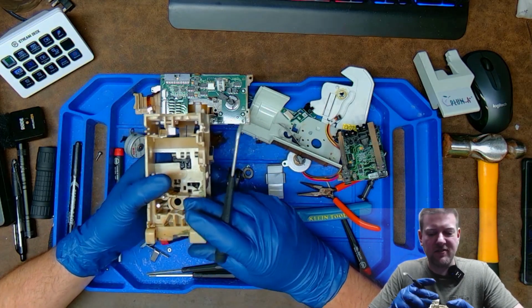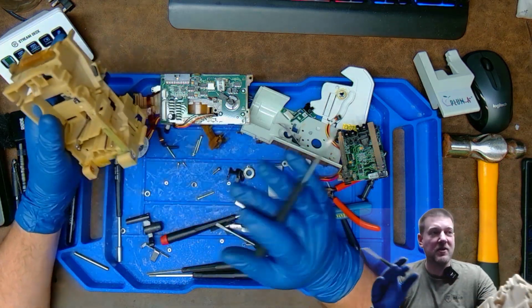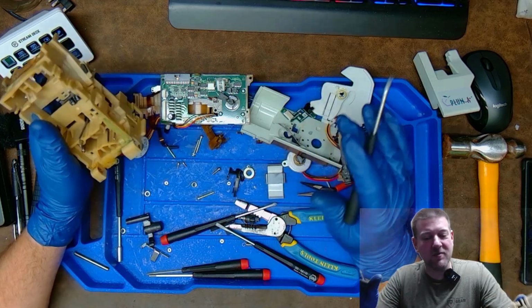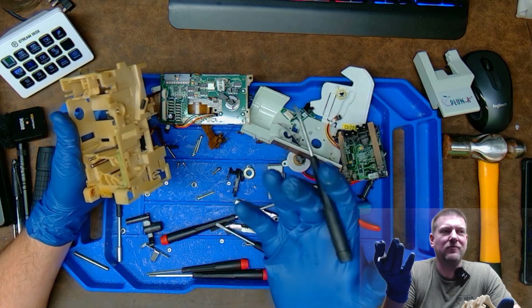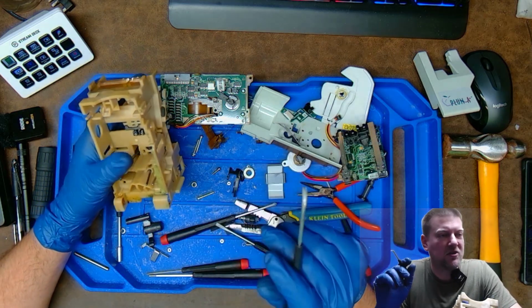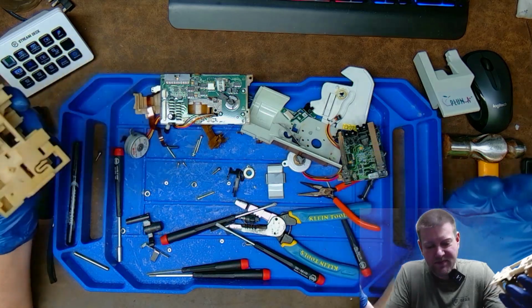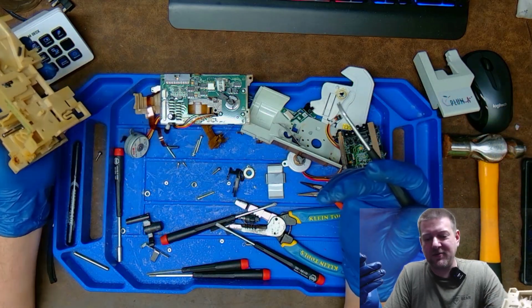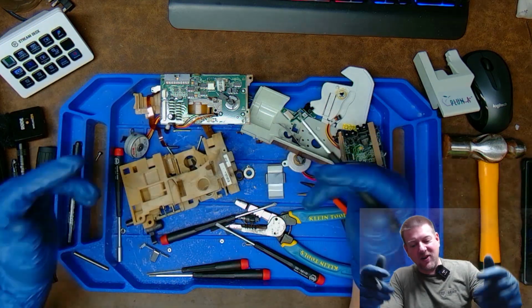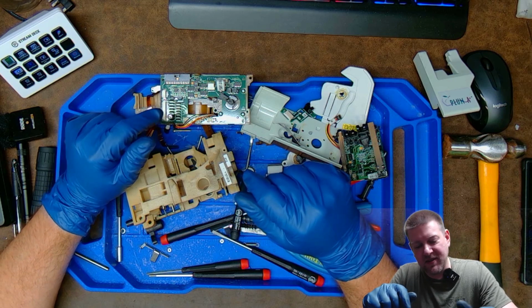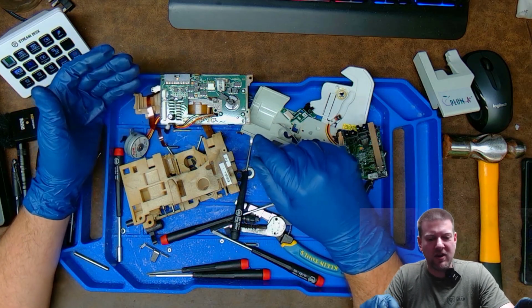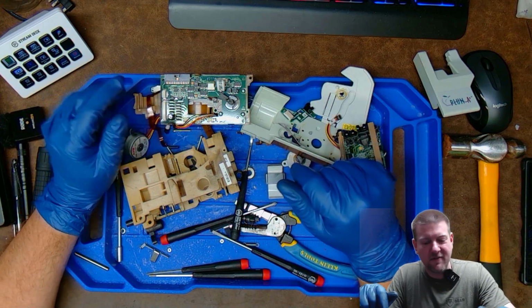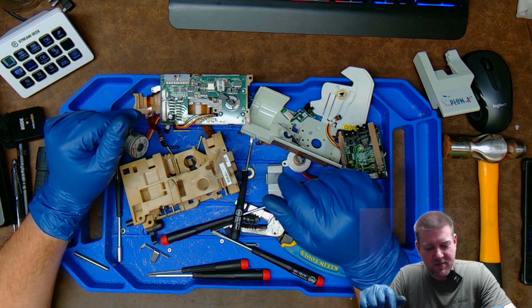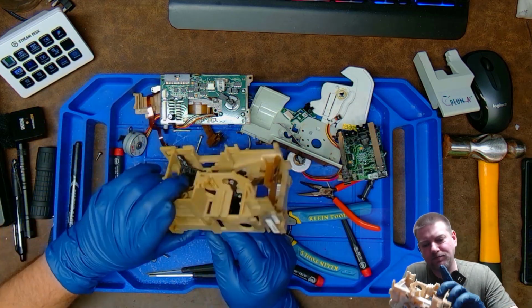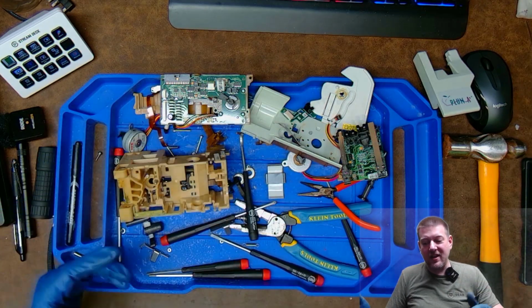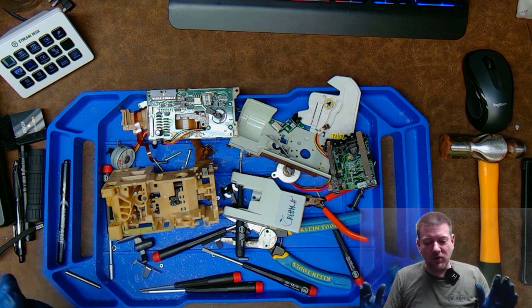These spring-loaded rods obviously actuate something in the infusion set. To be honest, I have never loaded one of these pumps up and run it. So normally when I look at a disposable infusion set, I look at all the crevices and all the precision measurement points, like the pressure transducer point and stuff. And these pumps here, I've never had the opportunity to work with them, and I just tear them apart. You know, Alaris is my bread and butter, B. Braun and some of the other pumps. These guys here, I've got people that work for me that are specialists in these pumps, and they know every little crevice of calibration for them and whatnot. But I myself, I do not. Interesting, fascinating little pump. Guys, the bill of materials on this pump module alone is insane.